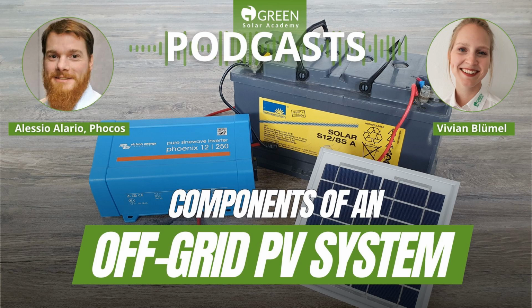And I would always recommend choosing a combination of off-grid inverter and grid inverter which has been successfully tested together before. So like manufacturers that produce both the grid-tied inverter and the off-grid inverter, or that have been approved by the manufacturers and tested in the field. That's right. I think the former, it's rare to find manufacturers which make good off-grid inverters and grid inverters. But certainly there's a lot more off-grid inverter manufacturers that have tested specific grid inverters to work well with their equipment, and that's what I would recommend.